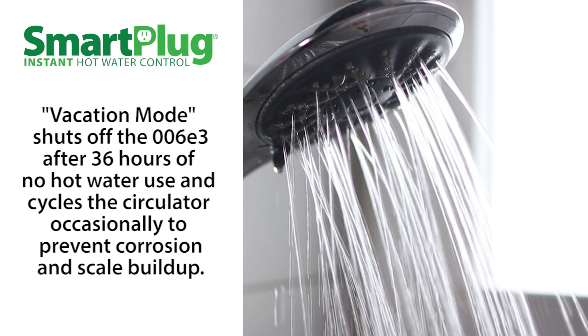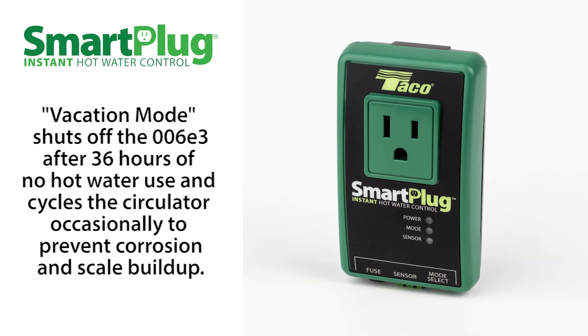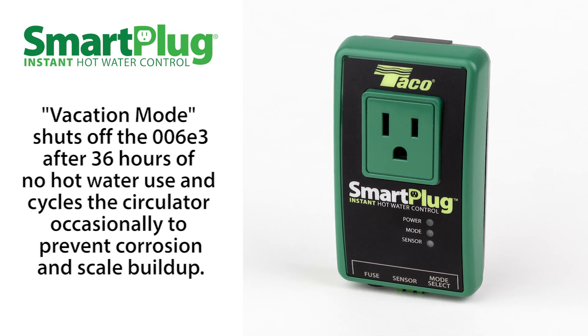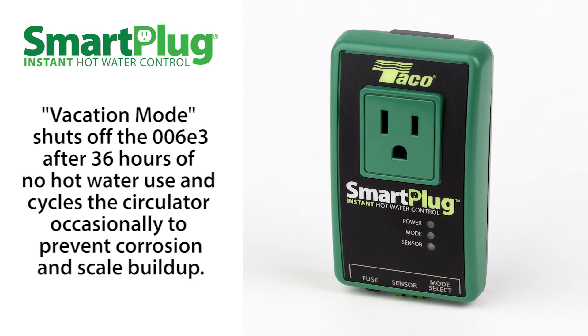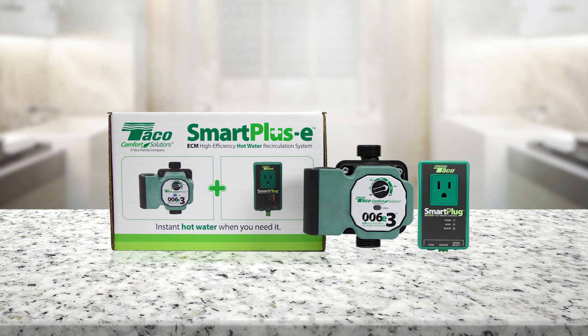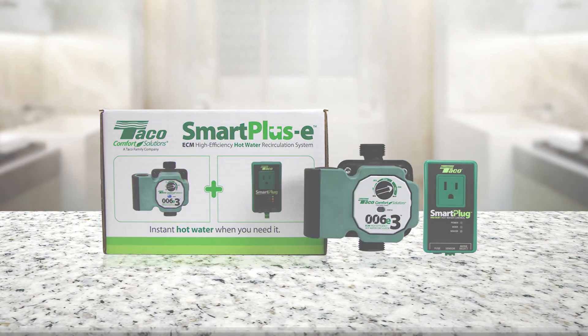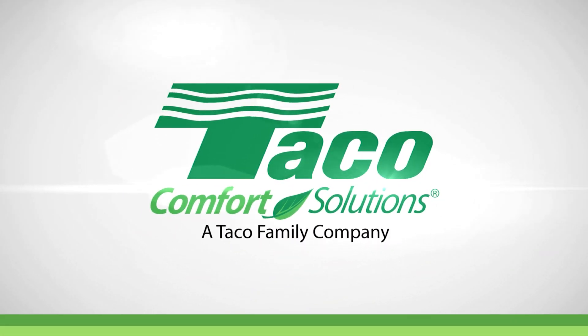The smart plug also features a vacation mode, which shuts off the circulator after 36 hours of no hot water use. While in vacation mode, the exercise function cycles the pump for 10 seconds every 7 days to prevent corrosion or scale buildup. For more information, take a look at the SmartPlus-e catalog sheet or log on to Taco's website at tacocomfort.com.